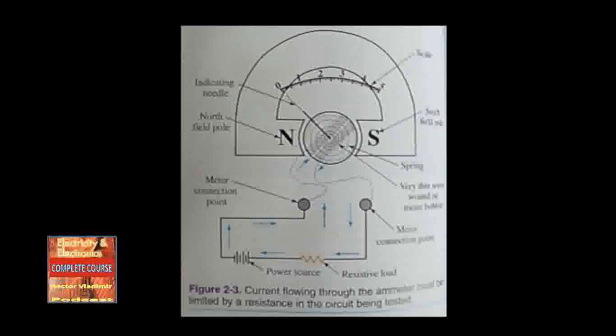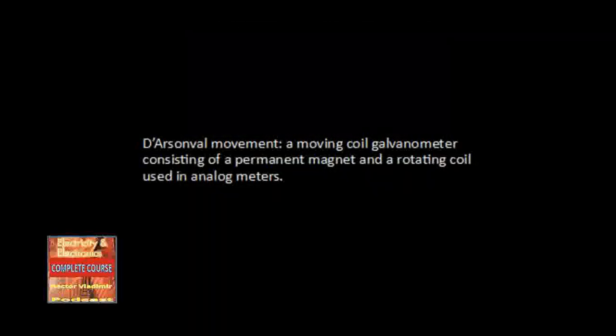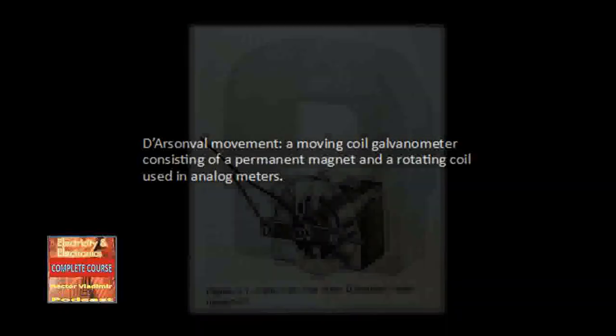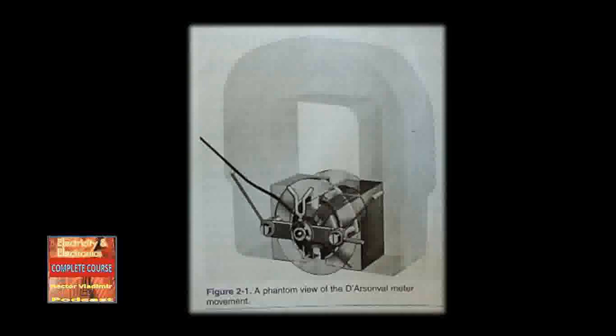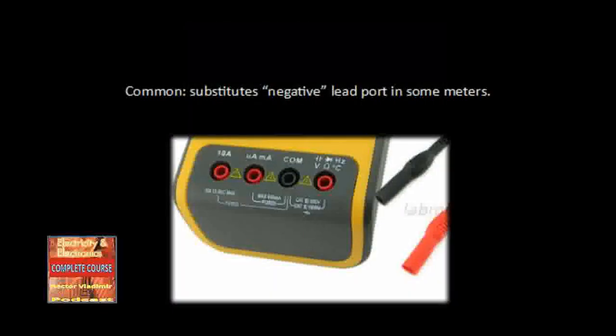The springs are also connected to the meter coil. The deflecting force rotates the coil against the restraining force of these springs. The coil that rotates in the magnetic field is mounted on precision jewel bearings, much like a fine watch. The jewel bearings, known as a D'Arsonval movement, make the instrument very easy to damage if dropped or jarred. Extreme caution should be used when transporting a meter with a D'Arsonval movement. When connecting the meter to an electrical circuit, proper polarity must be maintained. The meter is equipped with polarity markings — usually a red plus sign and a black negative sign. Some meters use the abbreviation COM, which stands for common, for the negative polarity marking.